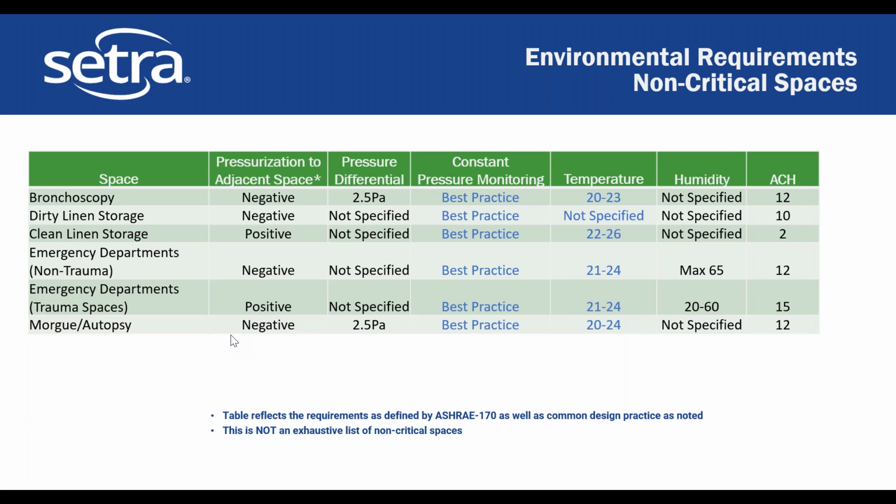An interesting note here is there's not an actual pressure differential requirement for some of these. It's just whether it's negative or positive and just making sure that that's the case. They do all still have temperature and humidity and air changes per hour. In these spaces, the best practice is often to just cover the pressure monitoring, but it does not hurt when you're having your inspection or your audit to have additional parameters there monitored.